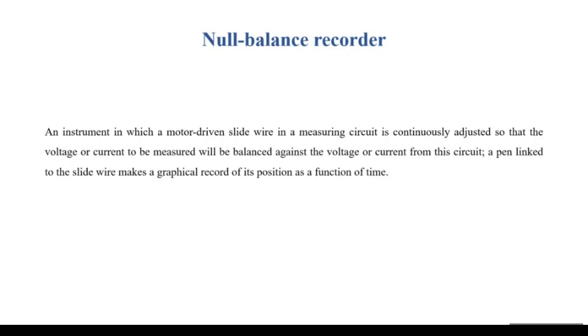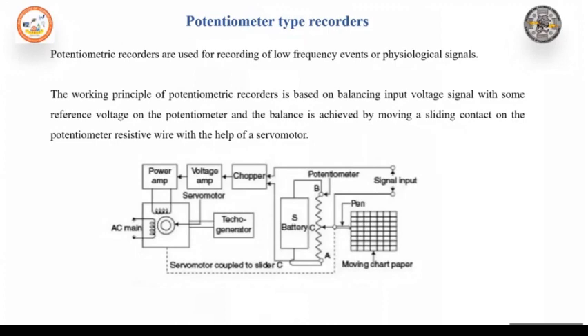With the appropriate scale factor, the indicator position on the output display scale indicates the magnitude of the input signal under measurement. Null balance recorders are of the following types: potentiometric type, bridge type, linear variable differential transformer type recorders. So let us discuss potentiometer type recorders. For potentiometric type recorders, I have shown the diagram here. The recorder of this type is basically a self-balancing potentiometer, which apart from the indication is also capable of permanently recording the values of the voltages as they are being measured.